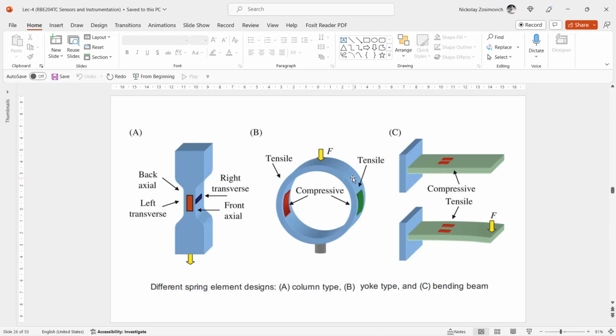The beam type spring element in figure C, on the right side of the slide, allows a differential mode measurement of the strain as well. Also, two strain gauges are sufficient, one on the top and one on the bottom, and four gauges are preferred to build up a full bridge.